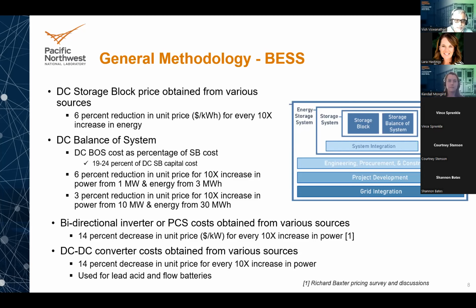We use a bidirectional inverter, or a fancier term, a power conversion system, and we assign a certain percentage decrease for every order of magnitude increase in power. For certain technologies like lead acid battery and flow batteries, we need a DC-DC converter to maintain a stable voltage, and we have a certain percentage decrease for every order of magnitude increase in power.